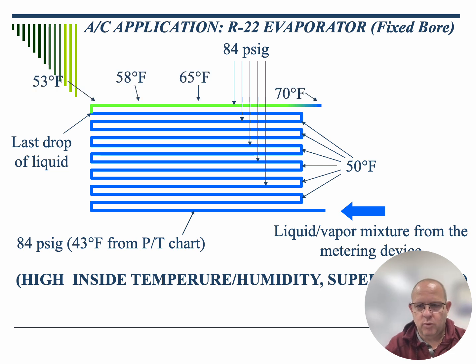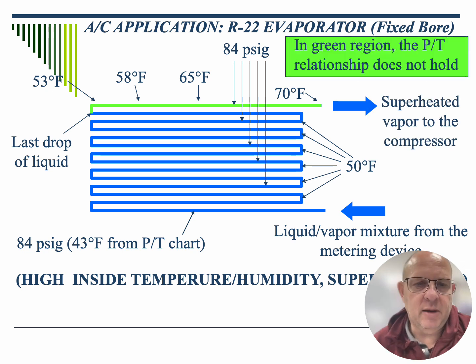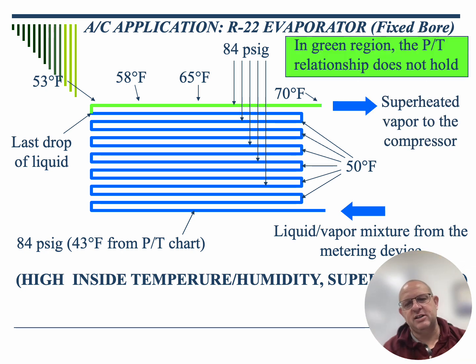On that particular system, we are getting 70 degrees coming back to the evaporator with the charge not changing at all, just an increase in the temperature and humidity within the living environment. And we can see that we are running somewhere around 20 degrees of superheat on this system. Just because your superheat's up doesn't mean that it needs more refrigerant. Just because your superheat is not within your desired number that's in your head doesn't mean that the system isn't properly charged. The same principle goes into this.